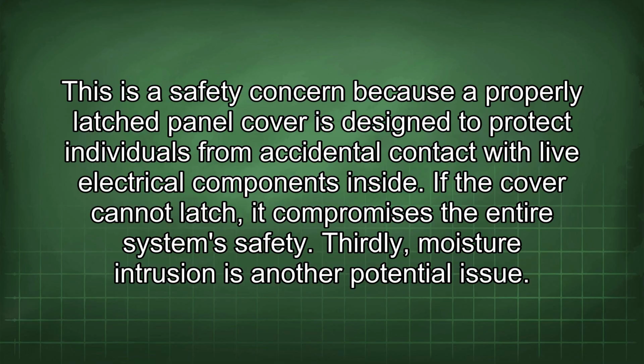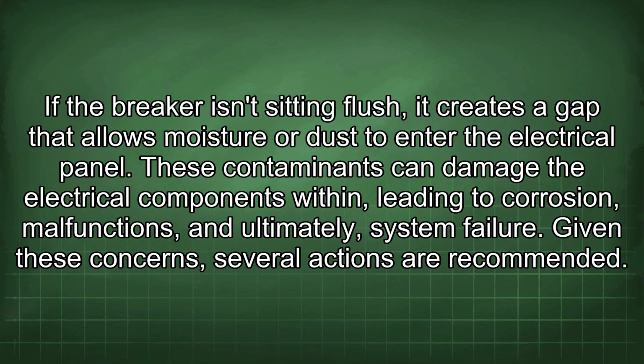Thirdly, moisture intrusion is another potential issue. If the breaker isn't sitting flush, it creates a gap that allows moisture or dust to enter the electrical panel. These contaminants can damage the electrical components within, leading to corrosion, malfunctions, and ultimately, system failure.